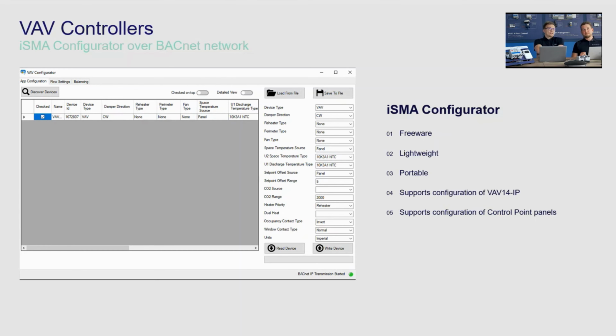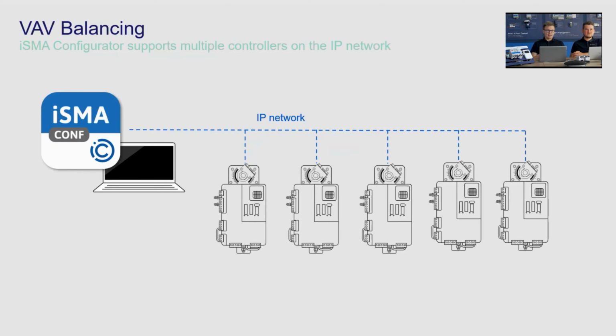Exactly. And iSMA Configurator recognizes two kinds of networks. We can easily connect using the USB cable just to the CP panel and make the configuration one by one, the configuration of the controller connected to the CP panel. But if we want to discover all the controllers available on the network, that's also possible. So it's quite powerful, even though it's freeware. I like it. But the balancing is a dedicated tab which allows you to balance the VAV controller. You can set the K-factor. You can set the minimum and maximum flow, do the zeroing of the sensor, and that's all. And manual override of dampers and sensor. So a manual override mode.